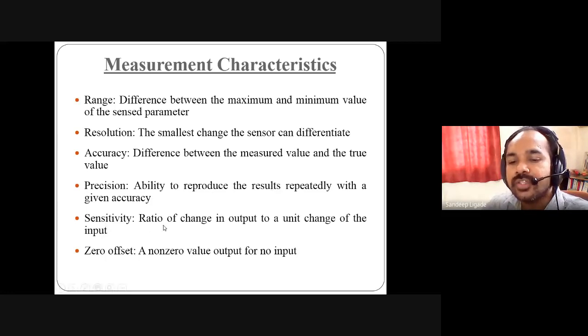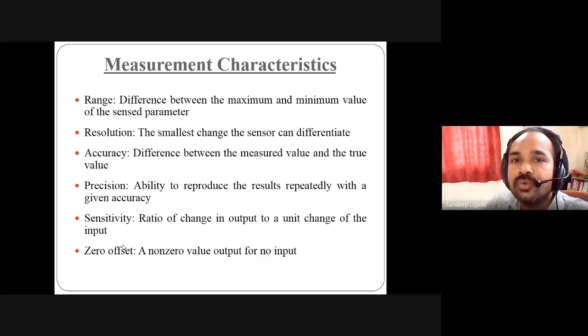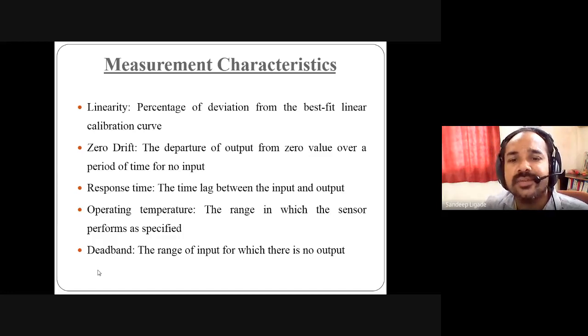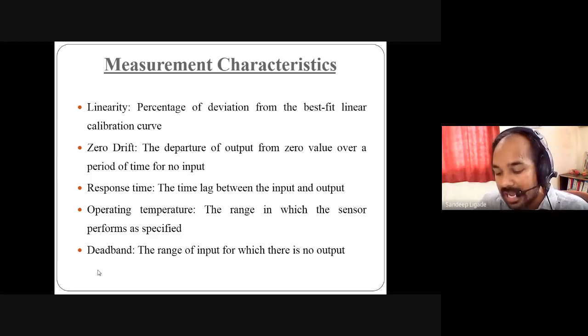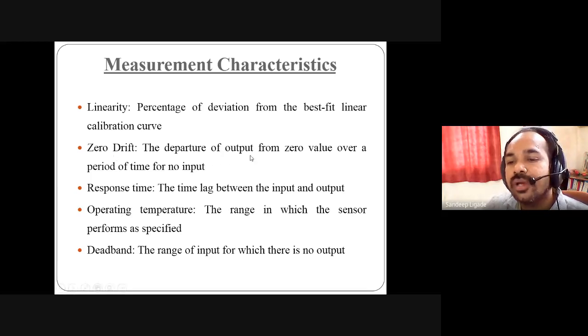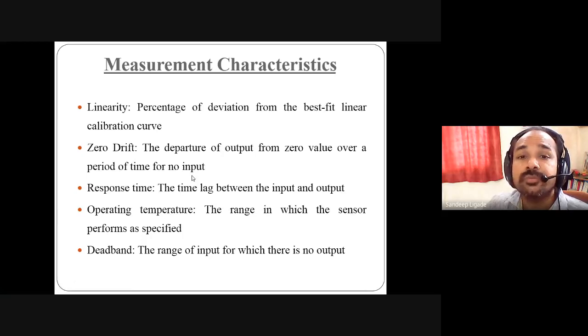Sensitivity is the ratio of change in output to a unit change in input — the sensor should be highly sensitive. Zero offset means a sensor with zero input should give zero output; a non-zero value for no input is undesirable. Linearity refers to the percentage of deviation from the best-fit linear calibration curve — values should be very close to the theoretical behavior or least squares fit. Zero drift is the departure of the output from zero value over a period of time for no input.